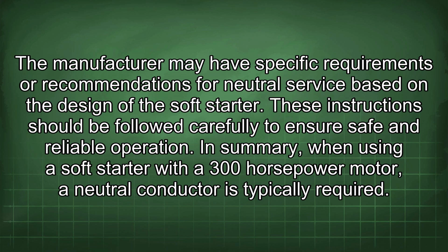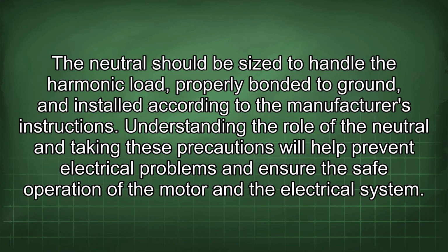In summary, when using a soft starter with a 300 horsepower motor, a neutral conductor is typically required. The neutral should be sized to handle the harmonic load, properly bonded to ground, and installed according to the manufacturer's instructions. Understanding the role of the neutral and taking these precautions will help prevent electrical problems and ensure the safe operation of the motor and the electrical system.